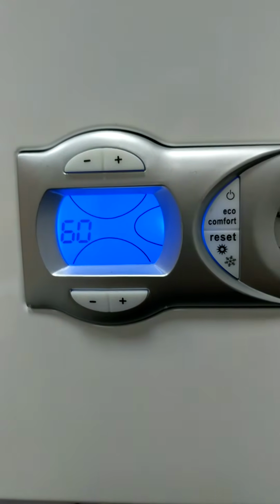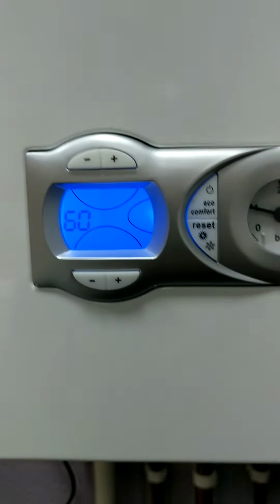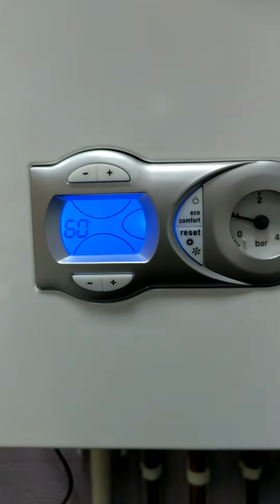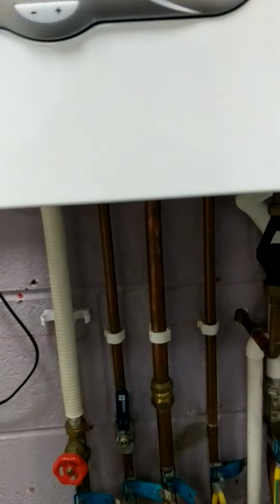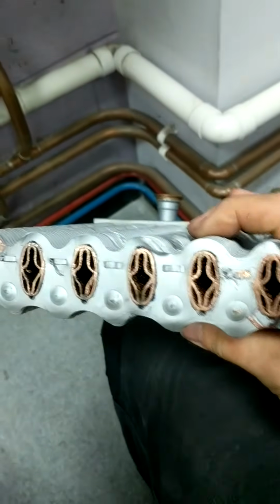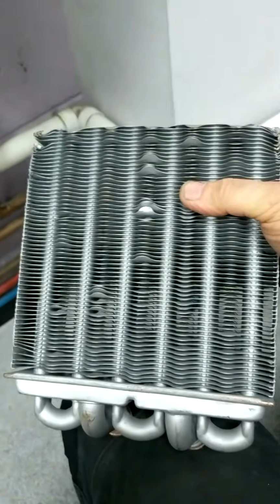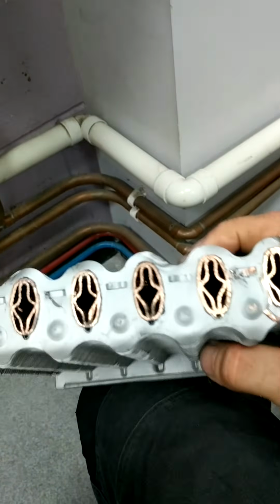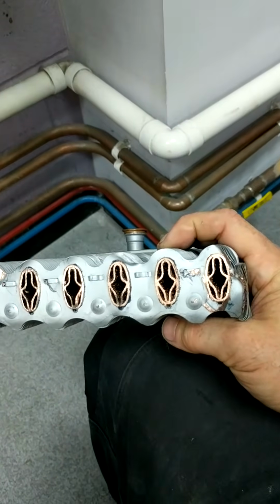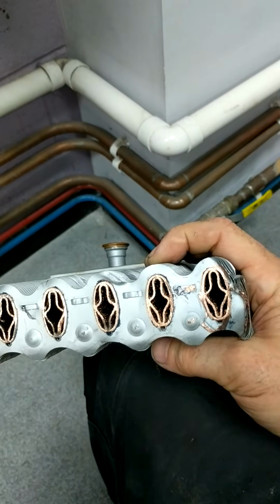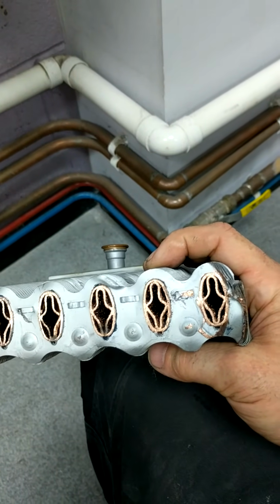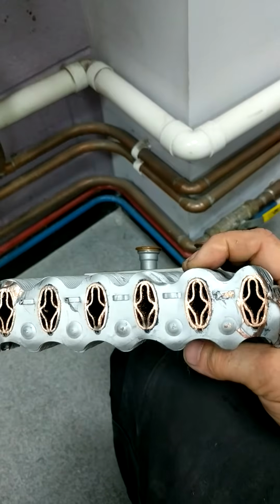You don't really need to go for 70% on this. The reason why, I've got a heat exchanger here which is cut in half. If you just have a look here, this is the actual heat exchanger on all these types of boilers. They're very, very small, and so when they come out of the factory, it's 20-odd percent, 20 kilowatts, 25 kilowatts, 29 I think is the highest one they've got.